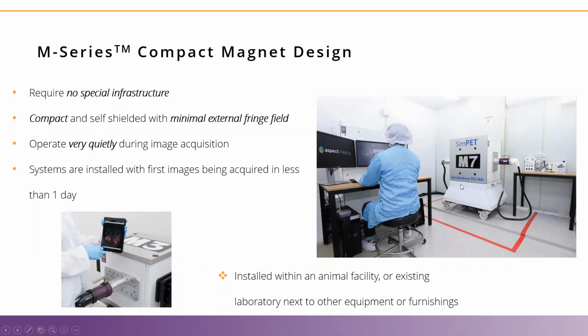The system itself is quite compact, but included in the exterior components of the system is shielding. And so that helps to minimize the amount of magnetic field which is experienced by the environment around the system itself. You can actually see on the floor here this red line. This is the 5 Gauss line. And that line is defined where someone with a pacemaker, for example, should not go in case it affects the sensitive medical equipment like a pacemaker that they have.